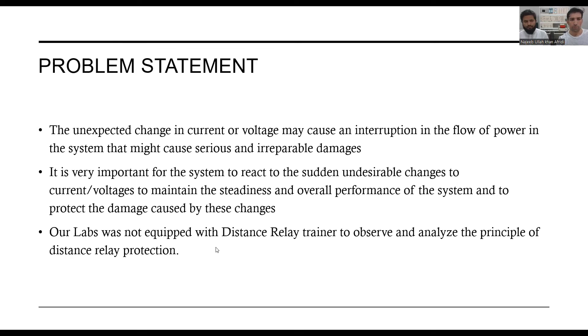What is the problem statement? As we know, transmission lines are the most vulnerable part of power system to faults. The unexpected changes in current and voltage may cause interruption in the flow of power in the system that might cause serious and irreparable damages. So it is very important for the system to react to sudden undesirable changes in current and voltage to maintain steadiness in overall performance of the system and to protect against the damages caused by these changes. One of the problems is also that our lab was not equipped with distance relay trainers to observe and analyze the principle of distance relay protection. So we are required to design a distance relay trainer.